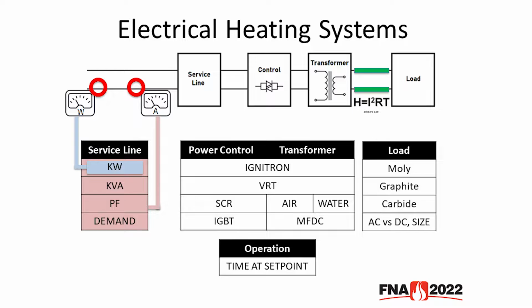Each of these control types has an ideal place for use, and it is important to consider the control type because it can have an impact on the upstream power quality and quantity. Next in the system is conversion to high current, low voltage with a transformer. Transformers are typically divided into air-cooled or water-cooled. The high current then needs to be delivered to the load. This can be accomplished through water-cooled cables or large copper cross-sections.